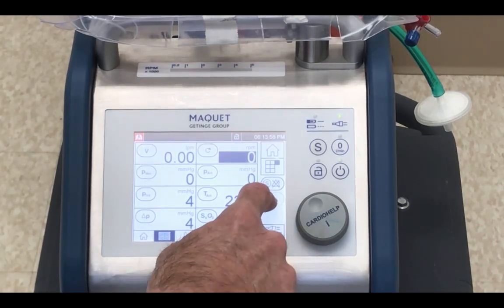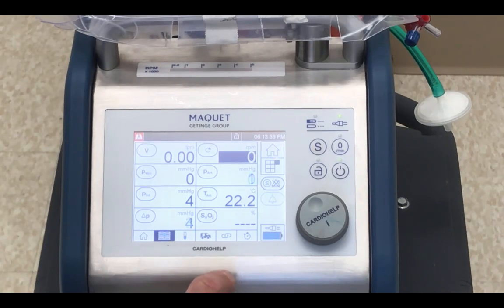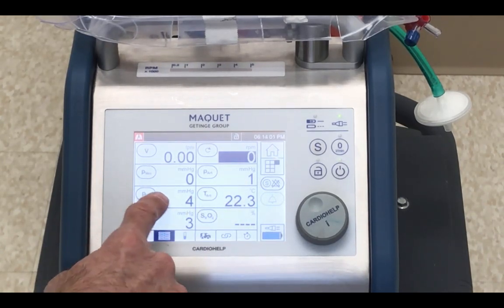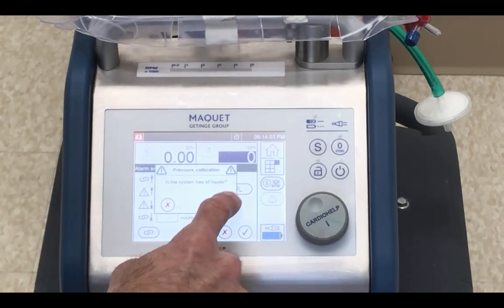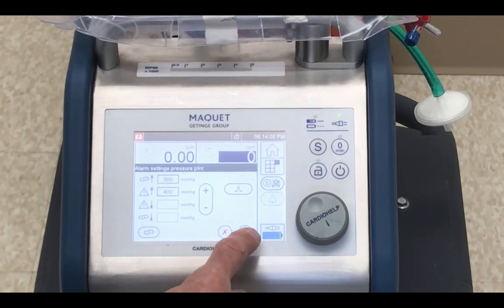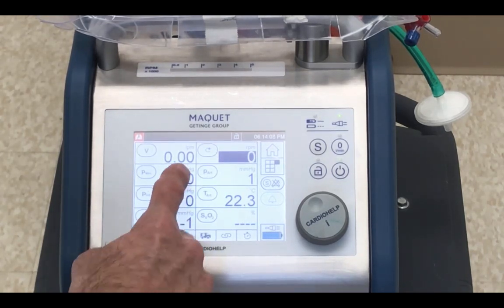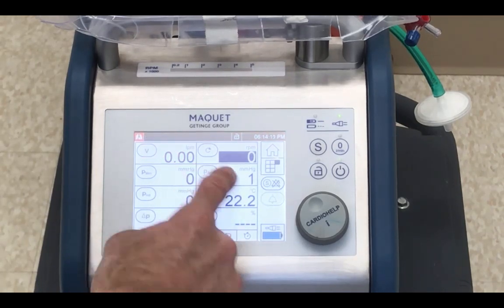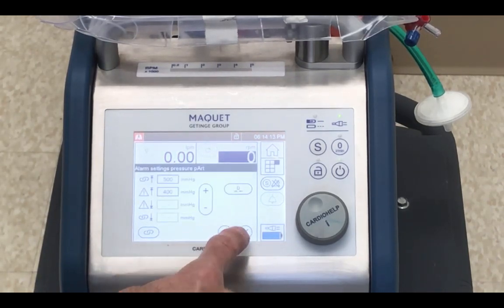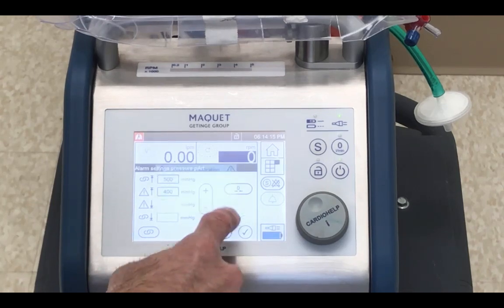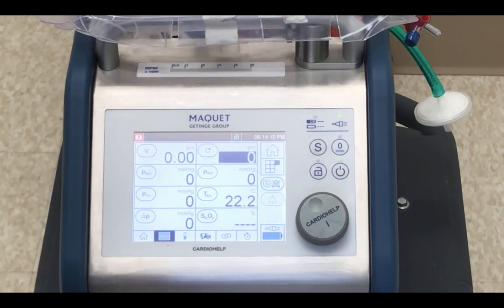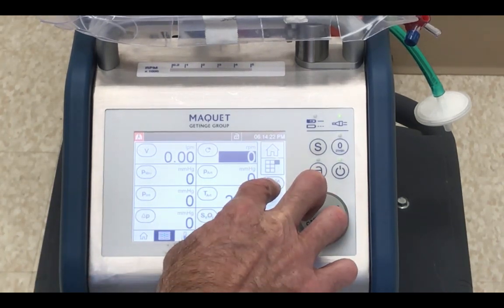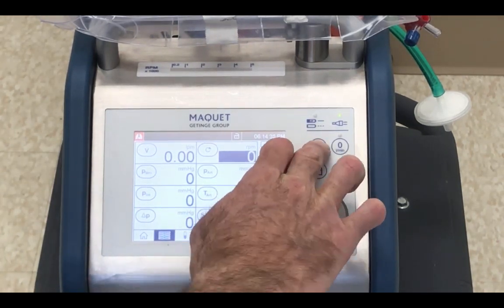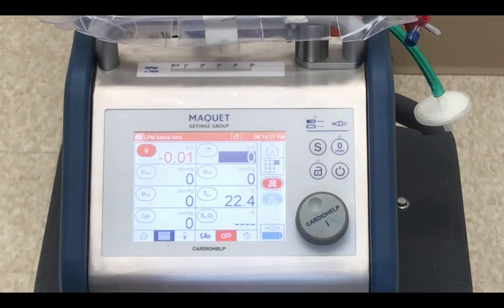Silence the alarm. Can't silence it yet. There we go. P internal. Zero that one. Close that screen. They should all read 0. Looks like P arterial still says 1, but it's pretty darn close. We would probably just leave that alone. There, all 3 of them are 0 now. With that taken care of, I think I can put this in global override so it'll be more quiet. And we can move on with the priming.